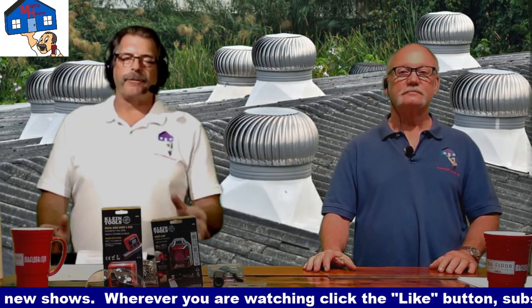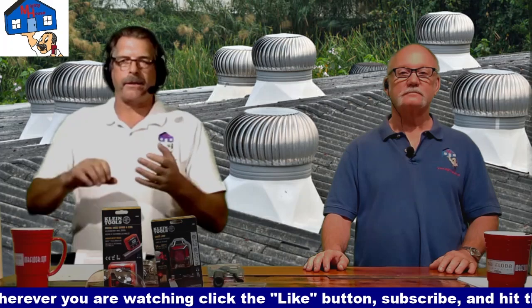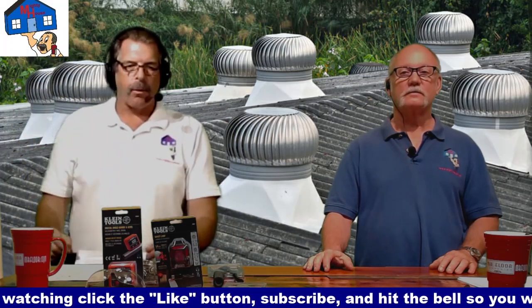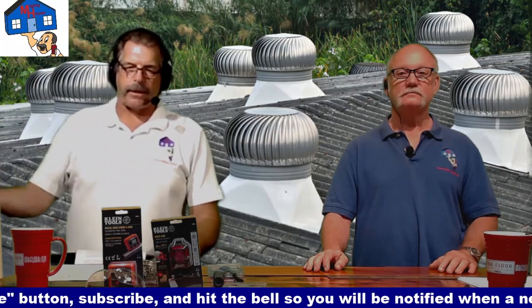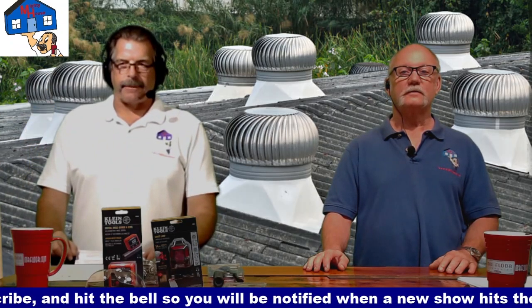Yeah. So on a 1,500 square foot ranch with a vapor barrier, which could be paint, could be a number of things to keep the ceiling from allowing too much air to go up, one square foot for every 300. I need 2.5 square feet in my attic and 2.5 square feet in my soffit. Got it. Now, this is where it gets dicey.